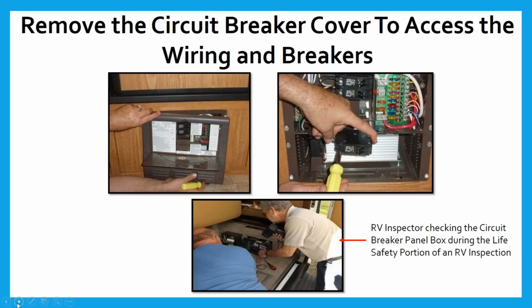So you want to make sure this power circuit breaker panel box is dead, no power coming in, and you're going to begin to go in here and start tightening things up. Now, we're not talking about playing gorilla and trying to break things, but what you're going to find on the circuit breakers, on the power strips—the terminal strips where the white wires and the ground wires all tie in—you'll be surprised how many times those strips have gotten worn. What happens is when they start getting warm, that wire expands and causes that screw to back up, and then when the wire gets cold, it pulls away. So now you have a gap between the screw and the wire, and you're going to go in there and retighten these things.